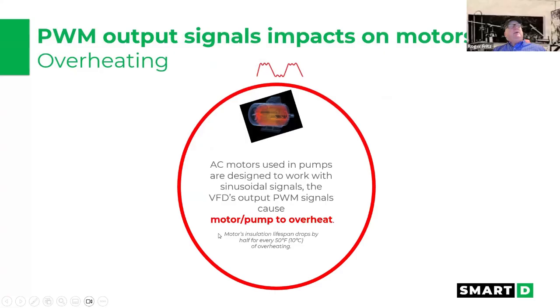From that, the PWM has an impact on the motors, in that it basically starts creating additional heat, because with all these jags here, the motor creates counter EMF and pushes back against this, but it doesn't exactly match, because it creates it based on a pure sine wave of the rotating speed of the motor. So these two start conflicting with each other, and that creates additional heat up inside the motor itself.